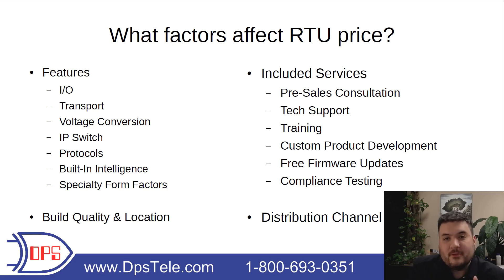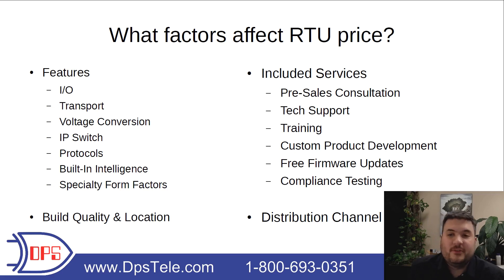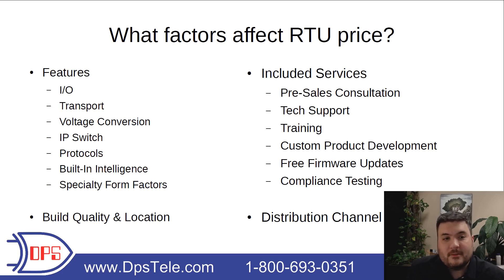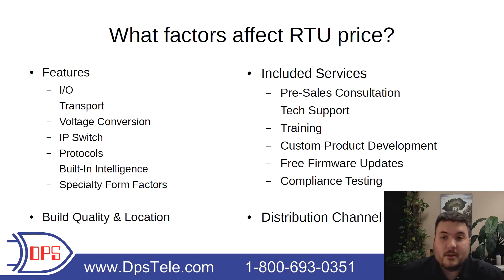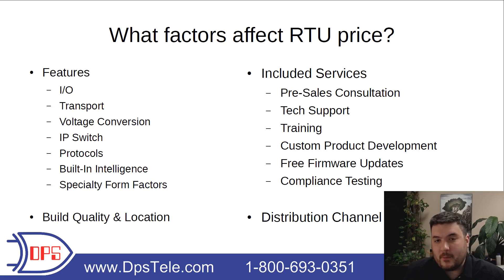If you need two, four, or eight discrete inputs to monitor doors, sensors, and equipment alarms, that's a fairly small RTU. But if you need 32 or 64, we're talking about a larger, more expensive RTU. For analogs, do you need any at all? And if you do, do you need one, two, eight, or 16? Same thing for control relays. That combination of how many you need in each of the three categories is probably one of the biggest factors affecting your RTU price.